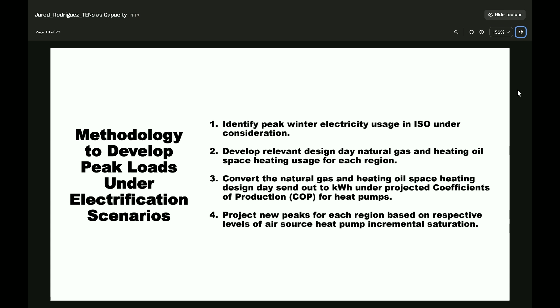You might look at an air source heat pump and they say it has a 3 or 3.5 average COP. But you have to know what the COP is during the design condition, the worst possible time. How much power will that system consume? I'm being generous with 1.5. If we use 1.5, we establish a new winter peak.